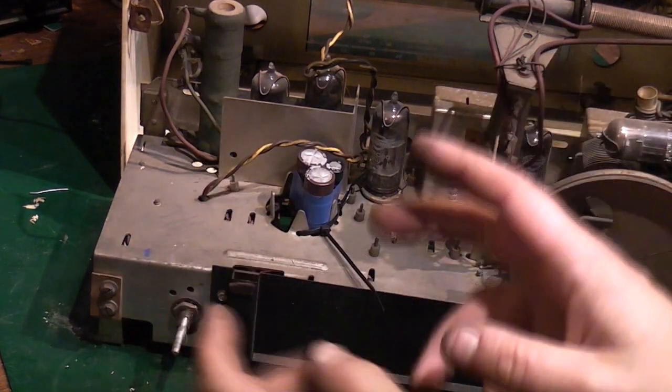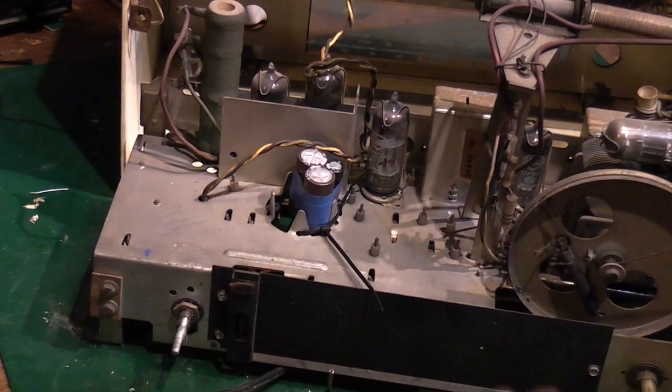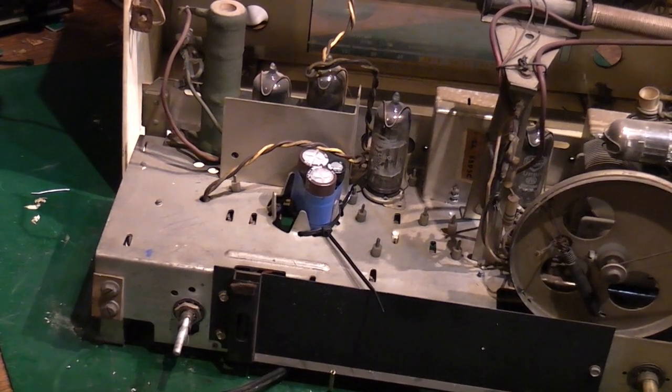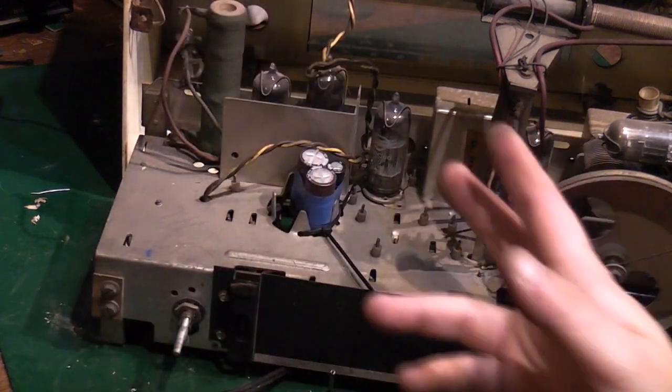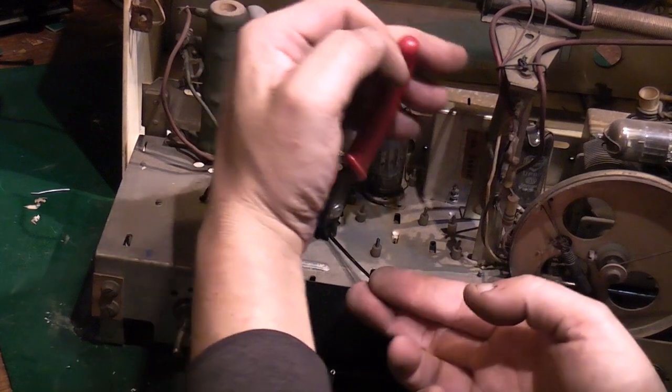They're not going to move around and risk one of them wires basically moving around and shorting to deck or anything. So we'll snip off the excess there. Yeah, is it the neatest repair? No. Is it a visible repair? Yeah. Is it going to work and is it safe? Absolutely.